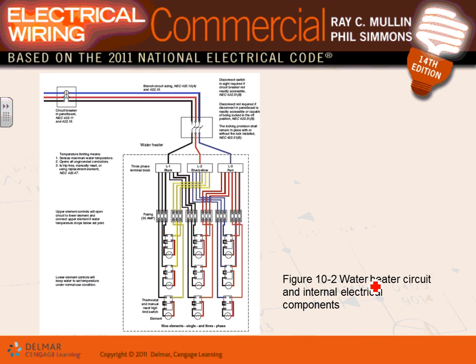This is how the water heater looks, guys. This happened to be actually three-phase, not the one that we did as single-phase. If it's three-phase, all you need is the conductors here, so that will be 1.25. The overcurrent protection device 1.5. You multiply by the amps.